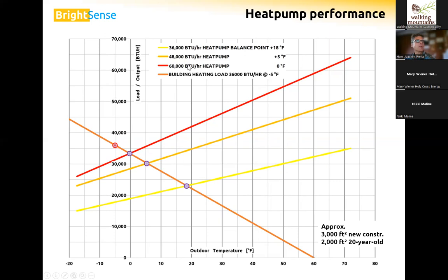So when we compare these heat pump outputs with the heating load of our home, where those curves meet, with the small one at plus 18 degrees, the medium size at plus 5 degrees, and the large one at 0 degrees, those are our so-called balance points. That means that the heat pump has enough capacity to heat this home down to this temperature on its own. And when it gets colder than that, we do need some supplemental heat.